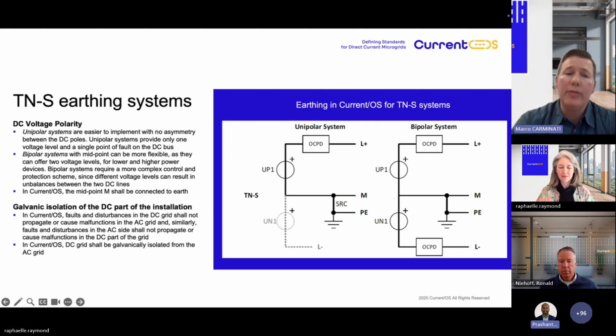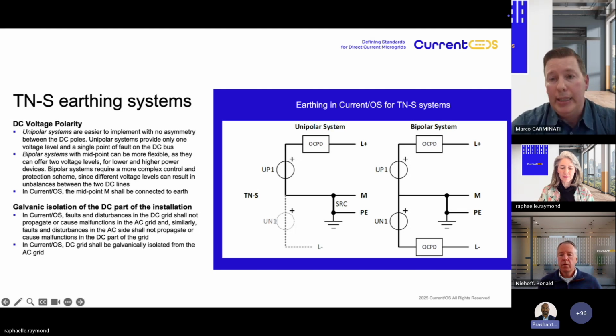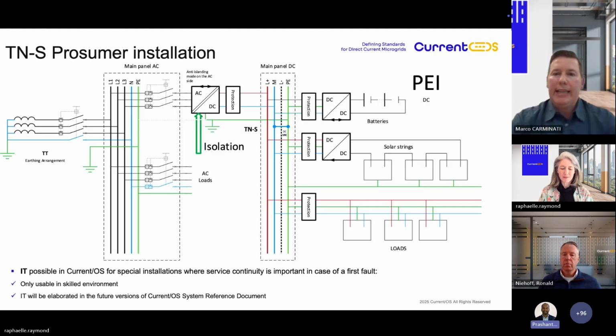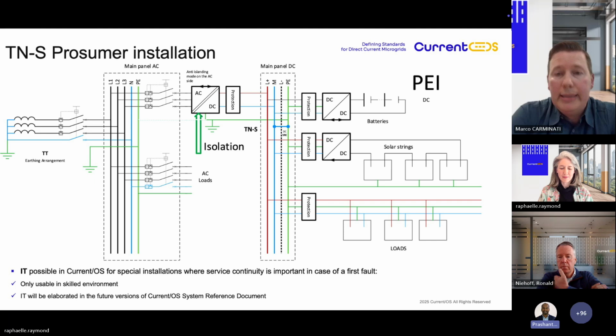In terms of galvanic isolation, as I was saying before during the earthing system explanation, the galvanic isolation is prescribed by Current OS in order not to have any mutual fault and disturbances between the DC grid and the AC grid. And moreover, we can decide to connect or not our DC side, no matter the AC earthing system. So this is the last slide from my side. Here you can see the typical TN-S distribution system with an isolated ILC.